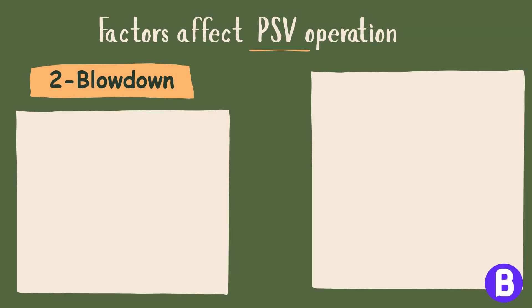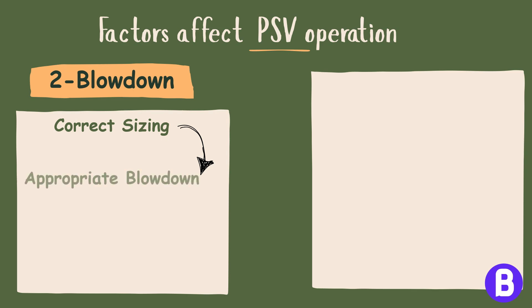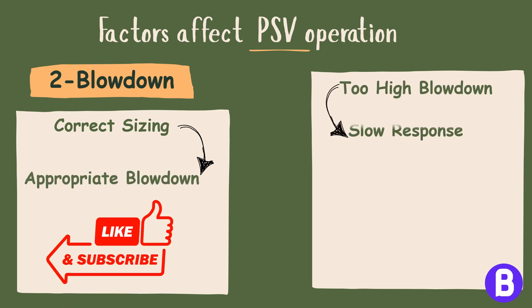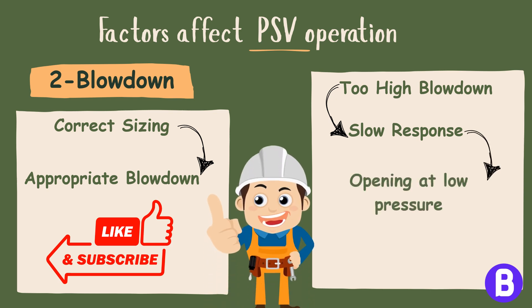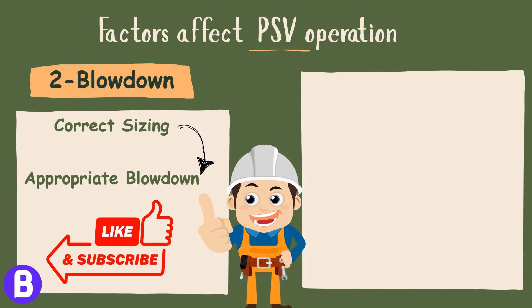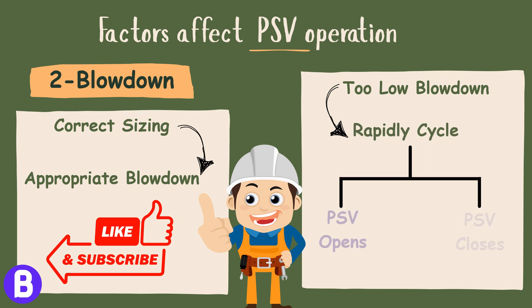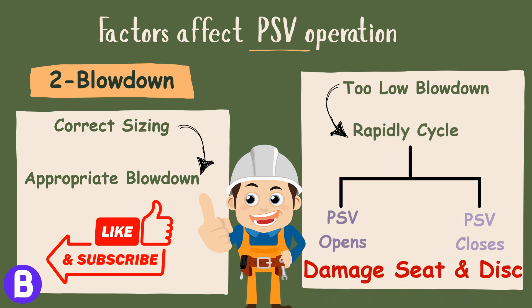It is essential to correctly size the pressure safety valve to have an appropriate blowdown. Too high a blowdown can cause slow PSV response and PSV closing at a pressure much less than set pressure, which can cause lots of disturbance. On the other hand, too low a blowdown shall lead the PSV to rapidly cycle between relieving and non-relieving states, leading to damage in the PSV seat and disc.